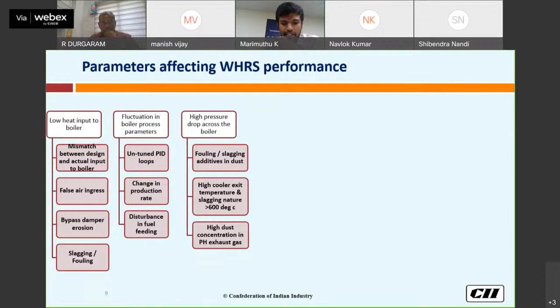And another one is high dust concentration in PH exit gas. Suppose the dust concentration is more, what will happen? It will foul on the tubes, and it will reduce the heat transfer. This is mainly because if my cyclone is not giving its efficiency as per the design, or if my dust collection system is not good, this will happen.